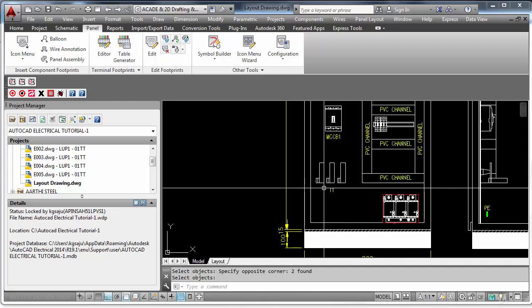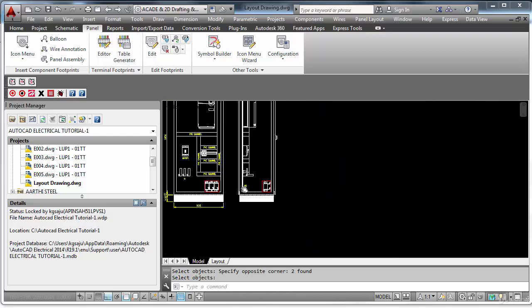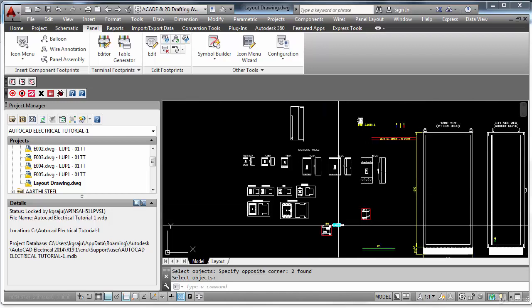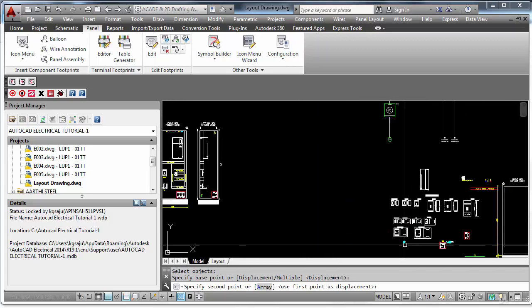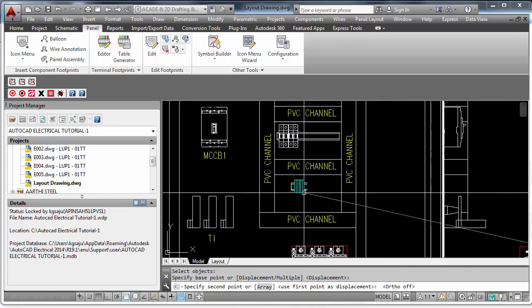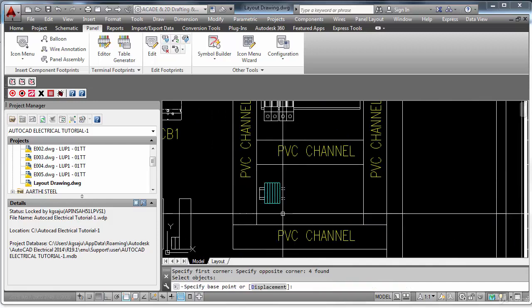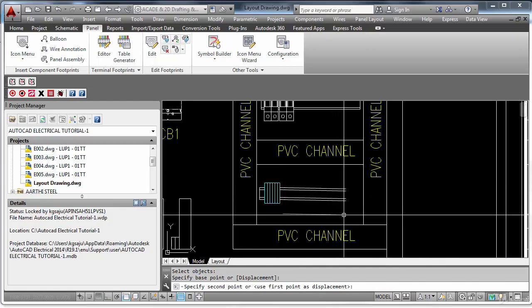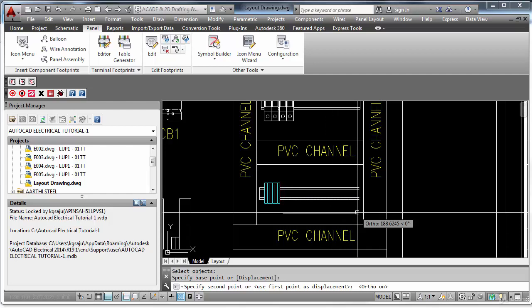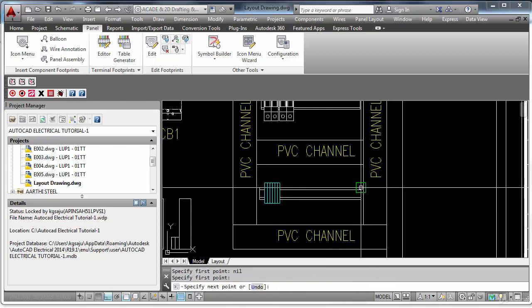And of course you can do the dimensioning, especially for these major things like the distance between the bottom and the termination. Many customers will ask you to give a clearance of 250, 300 mm minimum for power cables. And if it is control cables, you can adjust a little bit here and there. If I want to keep some control cables here, everything should be in one sheet so that you don't have to look for the blocks.